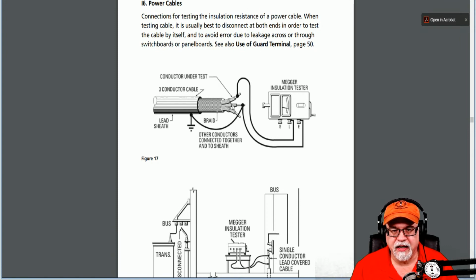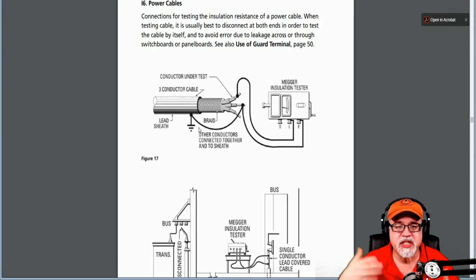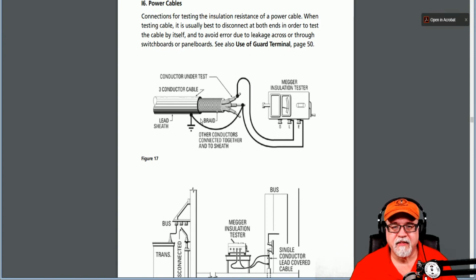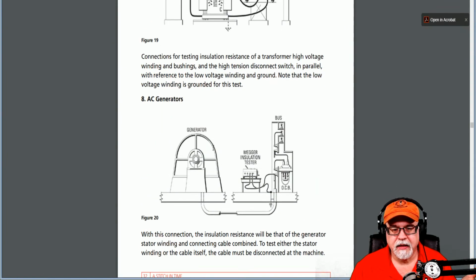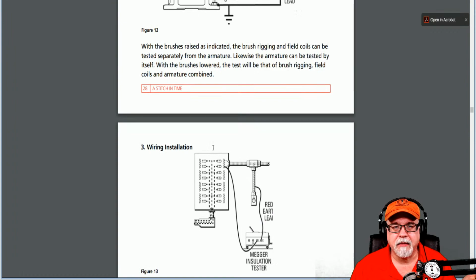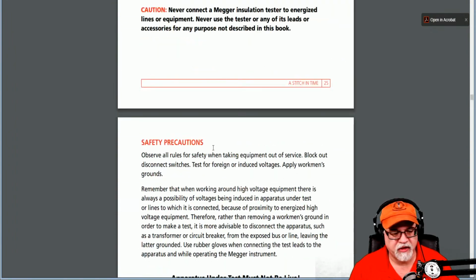Now we're testing this conductor, again, mutual damage, but we're also testing it to see that any insulation, the current that might be leaking out of it due to the voltage that's pressed into it, that we might get some kind of return path to this tester, okay? So even they talk about having a conductive outer core, okay? That sounds kind of like an oxymoron. A conductive outer sheathing, not the core, okay? So again, this is by their own document, all right? Now, this is just, again, not calling any individual, any company out. I'm just saying that's what they recommend, all right?